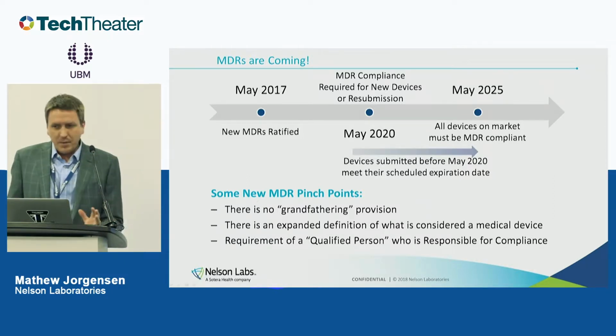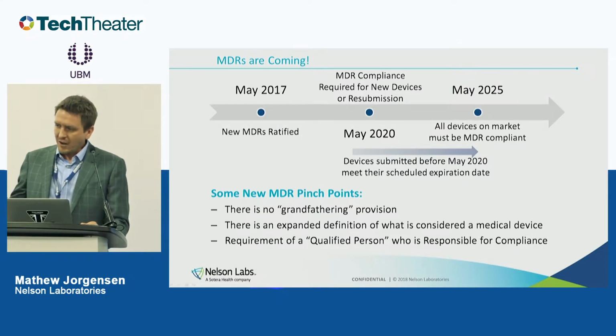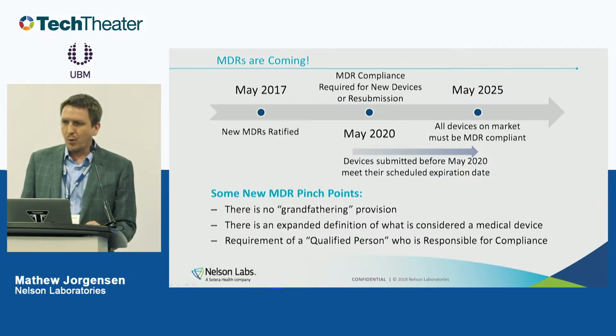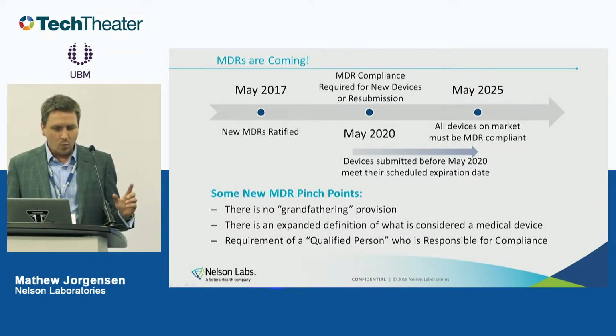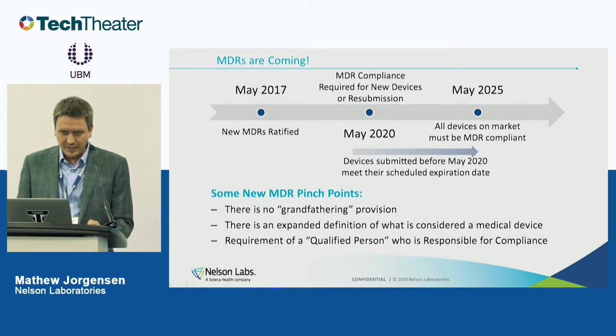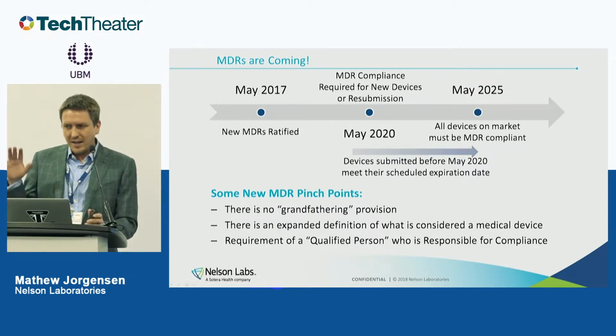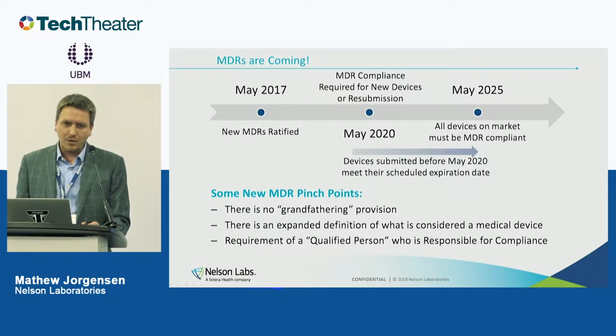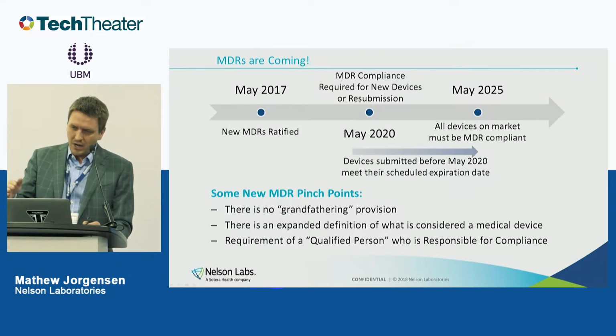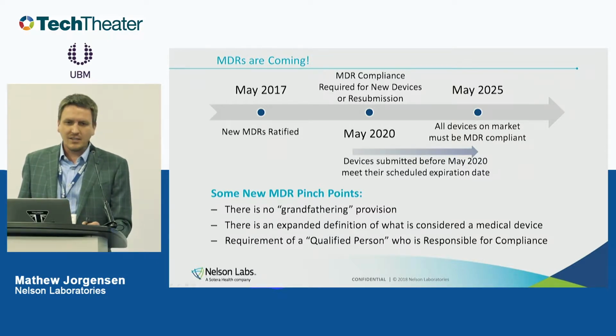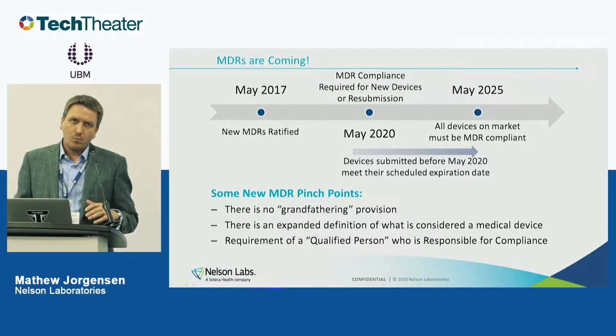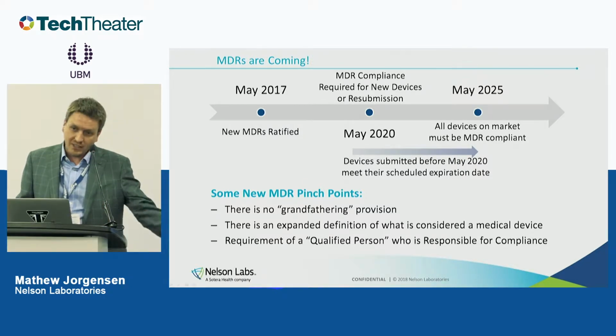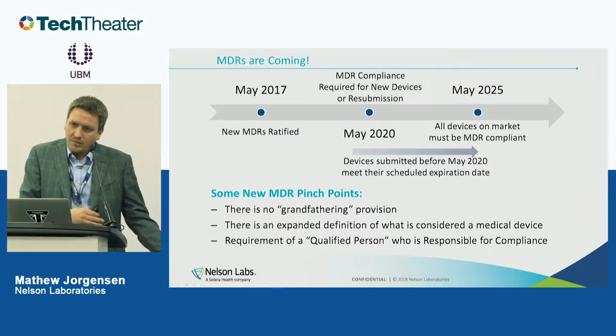Okay, so some of the pinch points with the new MDRs, if I take a whole bunch of pages of document and condense it down to 3 bullet points that seem to stick out to me, one is that there's no grandfathering provision. So what that means is that even if you've had a device on the market for a really, really long time in Europe and you've supported its safety because it's been on the market for a long time, that's not good enough to let it stay on the market, because they could say, well, the old rules weren't always perfect at protecting patient safety. So how do we know that when this device first was on the market, it was actually safe or not?